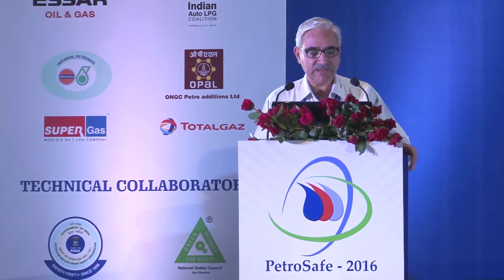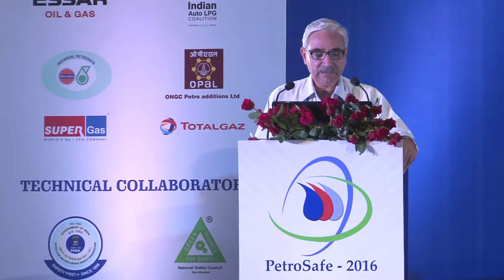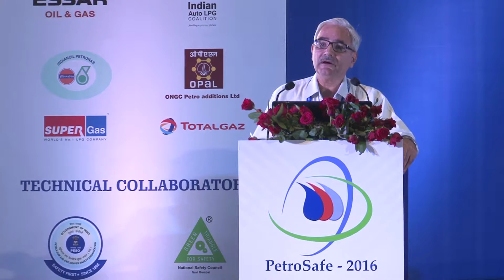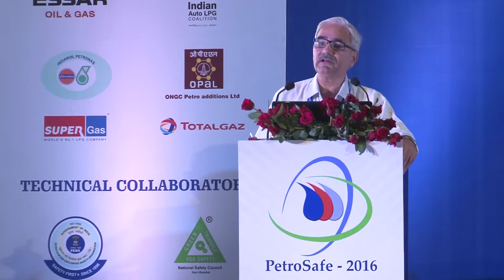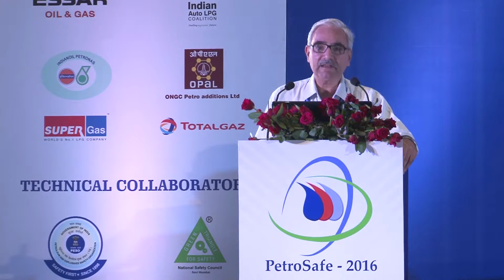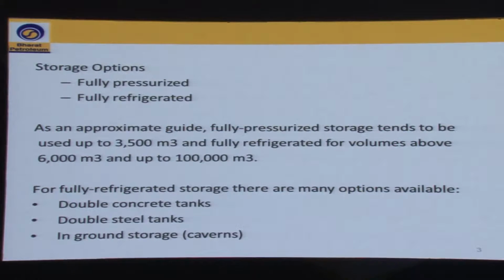As an approximate guide, fully pressurized storage tanks are normally used for a capacity up to 3,500 meter cube, while cryogenic condition is used up to 1 lakh meter cube. In the cryogenic condition, the tanks are basically atmospheric storage tanks and not pressure vessels, and they have to be double containment vessels. It can be a double concrete wall, or a double steel wall, or it can be underground caverns also.